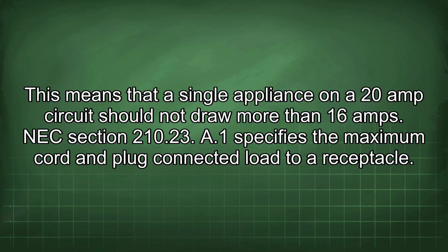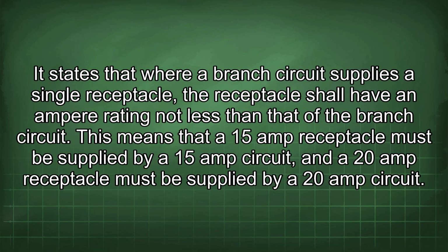NEC Section 210.23(A)(1) specifies the maximum cord and plug connected load to a receptacle. It states that where a branch circuit supplies a single receptacle, the receptacle shall have an ampere rating not less than that of the branch circuit. This means that a 15 amp receptacle must be supplied by a 15 amp circuit, and a 20 amp receptacle must be supplied by a 20 amp circuit.